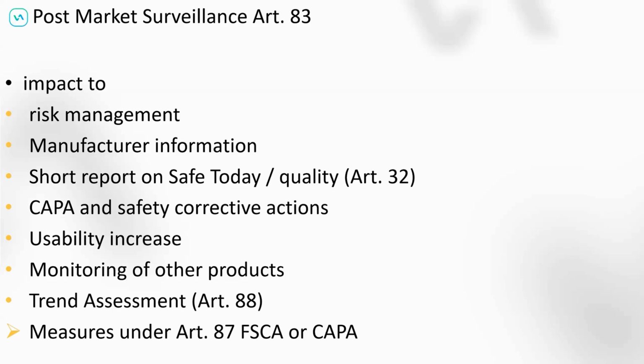The trend assessment, Article 88. The MDR has a very nice article, and therefore very nice requirements for what you need to do for trends of medical devices, how to evaluate if it's a trend or not. It is quite a simple and straightforward way if you know how to do that. We have seen many manufacturers who are not able to see what is a trend. They looked into that and said, hey, it is a trend already if I have a statistical increase of a certain issue.